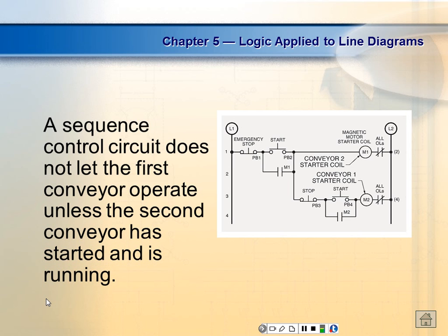So we have low energy circuits here, even though we're dealing with 240 and 120. The 120 is fused by a 1 amp fuse, so it's a very low energy circuit, right? You understand? These guys are fused with 10 amps. That means the inrush on these, even though these are quarter horsepower motors, if they start 2 of these at the same time, it's going to blow these fuses right here. Won't blow this fuse, because this is control, right? You understand?